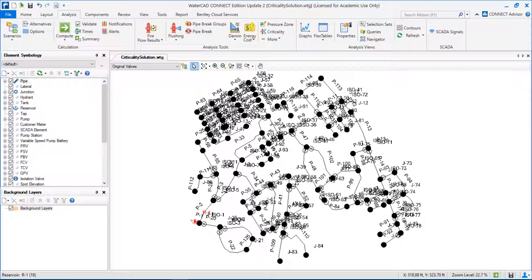Basically, how many customers will be affected without water? How will the downstream network length be affected? With this, we can try to understand where the critical segments or critical pipes are that we should look at and analyze, and if something like that happens in the future, how we can try to minimize the risk or consequences. Some solutions include better placement of isolation valves.